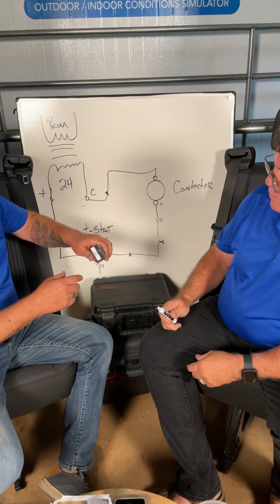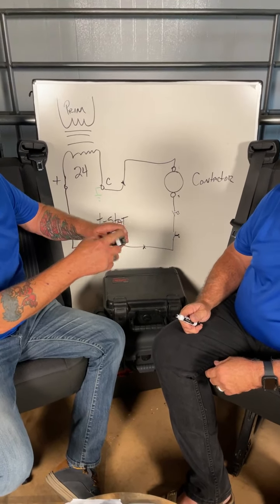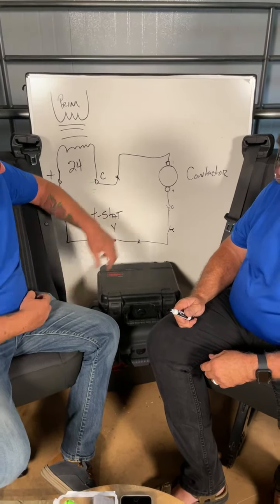That's these connections, because one of these switches could be open. Or a lot of times, when you're looking in the condensing unit, you're going to see a connector where they connect one wire coming off the low pressure switch and one wire coming off the high pressure switch, and they have a plastic connector. We're going to get into that too, the difference between ohms and continuity. Continuity makes sound, ohms is a reading.